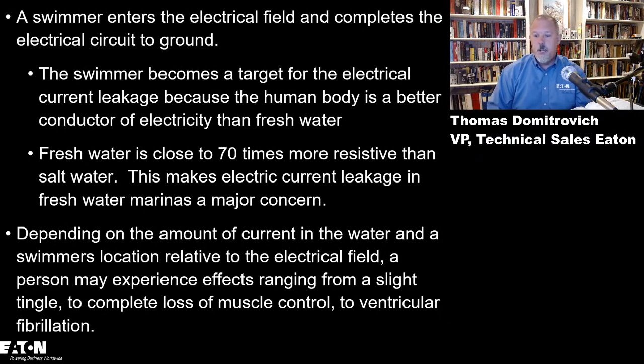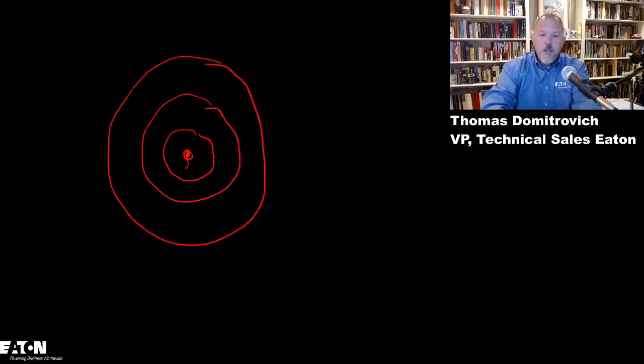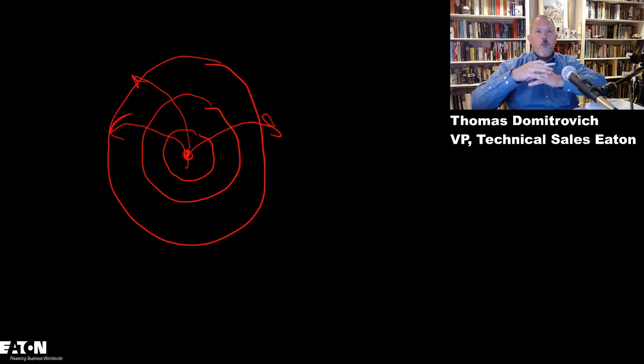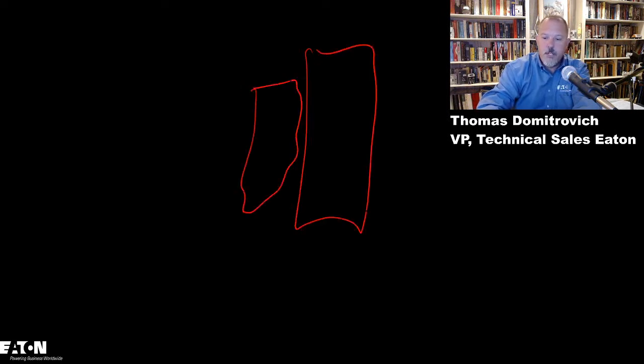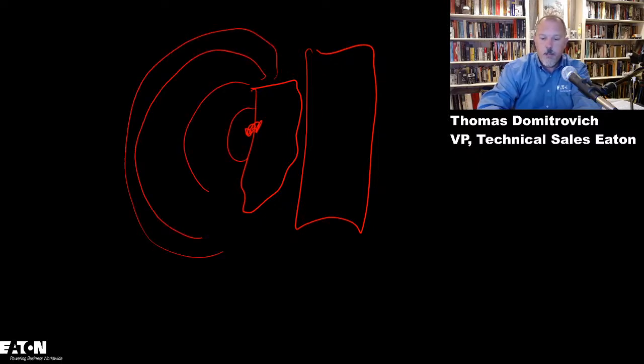Their argument was about the radius of that zone. If you think about what's going on, if I have an electric source in water at this point, I will get rings of gradients where current is flowing back to the source. So if I have a pier and a boat parked here, and there's a fault at this point in the water, I will have those gradients, rings of circles of magnetic forces, or current, trying to get back to the source. As a swimmer swims into that, they're swimming into that range.